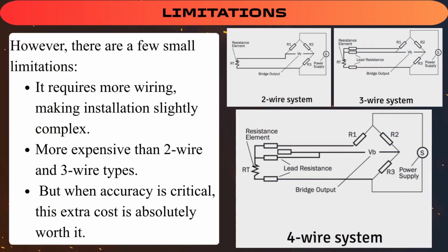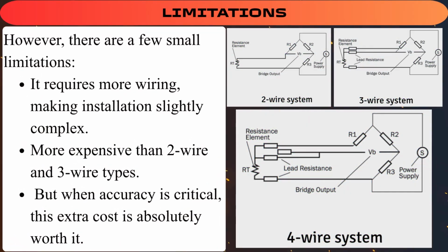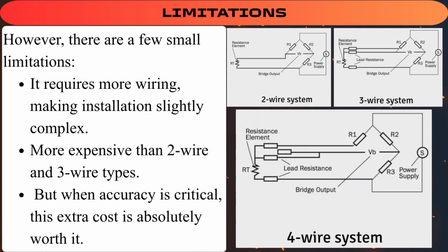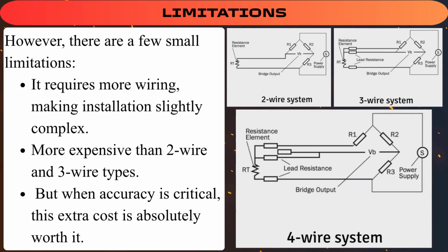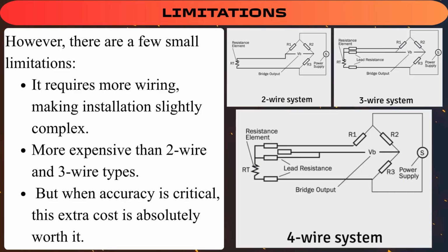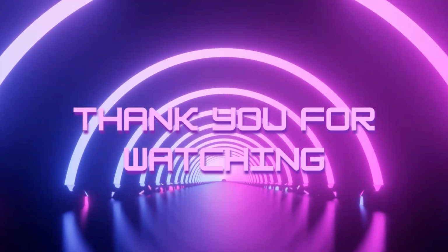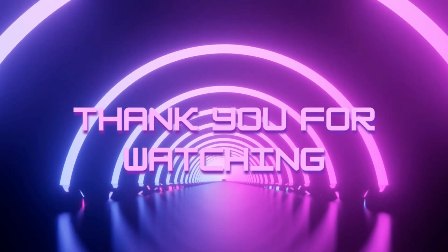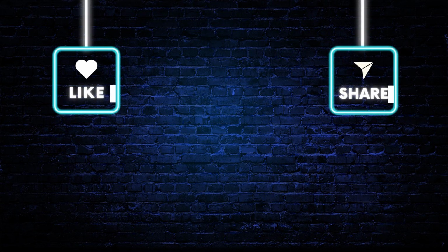Limitations. However, there are a few small limitations. It requires more wiring, making installation slightly complex, and it is more expensive than 2-wire and 3-wire types. But when accuracy is critical, this extra cost is absolutely worth it. I hope you now clearly understand how a 4-wire RTD connection works and why it's so important in industry.